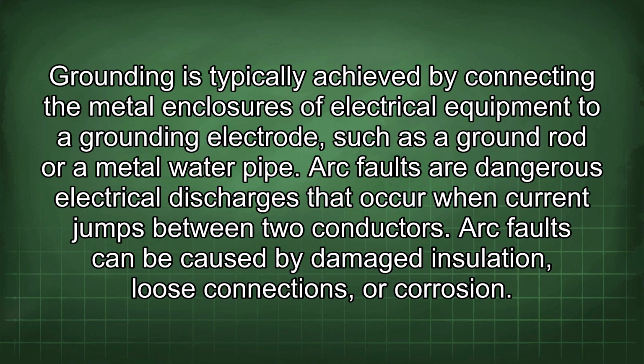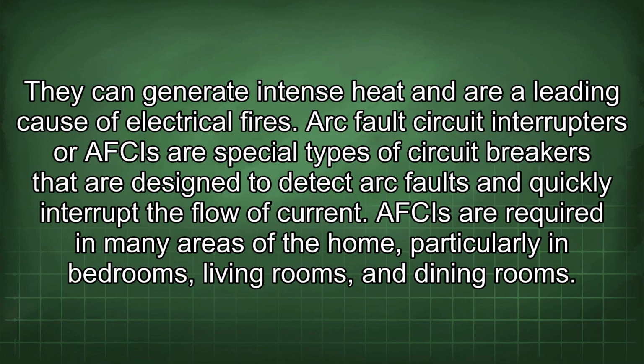Arc faults are dangerous electrical discharges that occur when current jumps between two conductors. Arc faults can be caused by damaged insulation, loose connections, or corrosion. They can generate intense heat and are a leading cause of electrical fires. Arc fault circuit interrupters, or AFCIs, are special types of circuit breakers that are designed to detect arc faults and quickly interrupt the flow of current. AFCIs are required in many areas of the home, particularly in bedrooms, living rooms, and dining rooms.